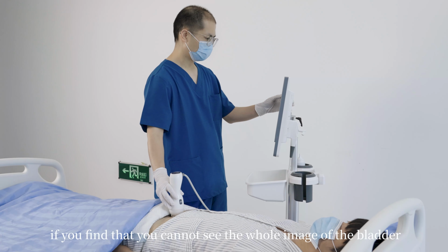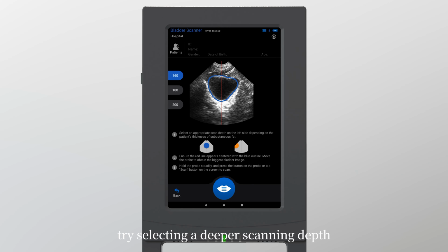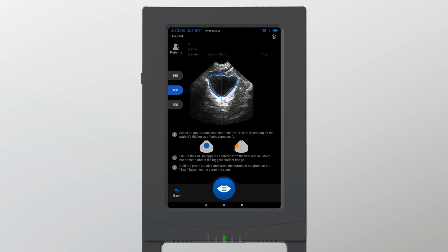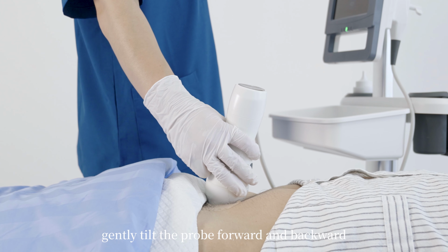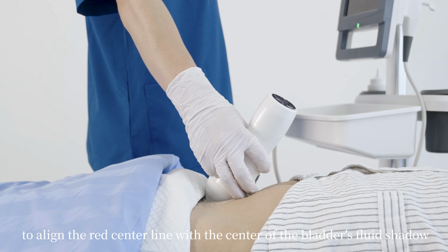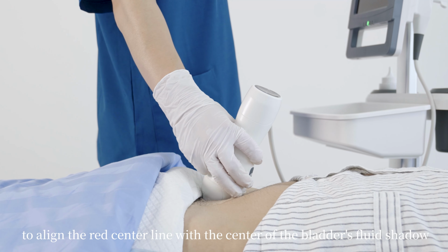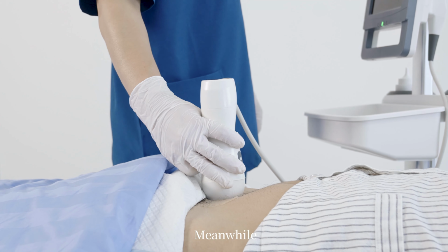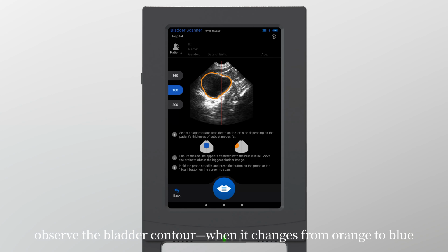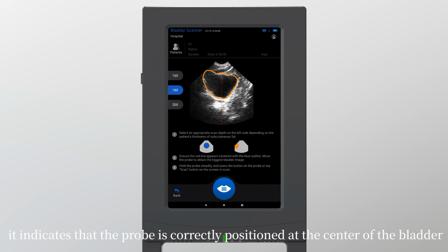Observe the image. If you find that you cannot see the whole image of the bladder, try selecting a deeper scanning depth. Ideally, the bladder should now be visible. If so, make sure it is centered. Gently tilt the probe forward and backward to align the red center line with the center of the bladder's fluid shadow. Meanwhile, observe the bladder contour.